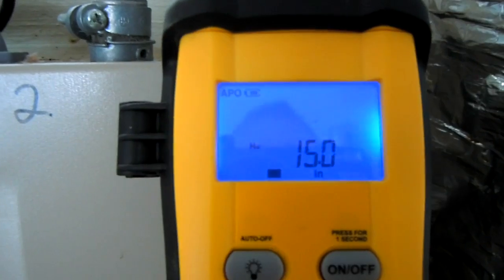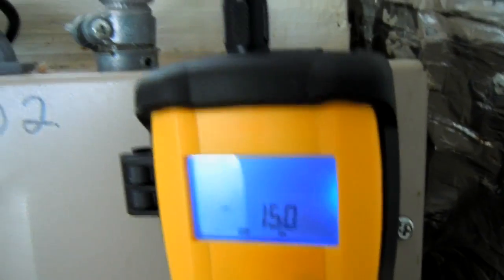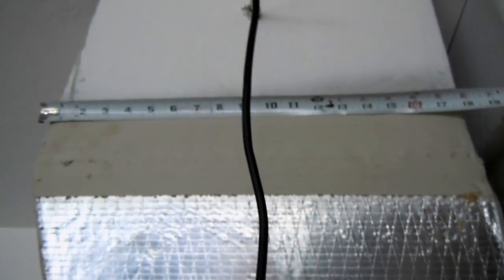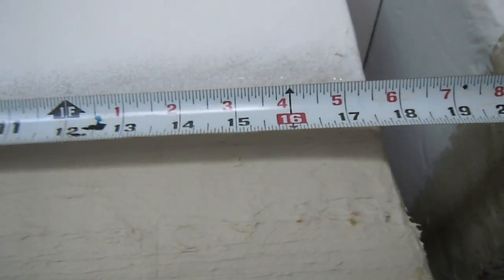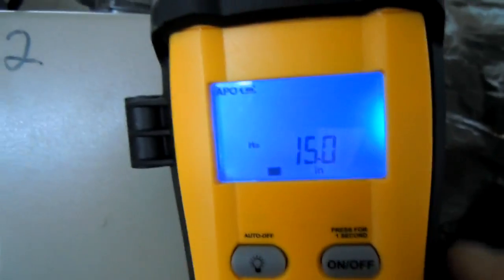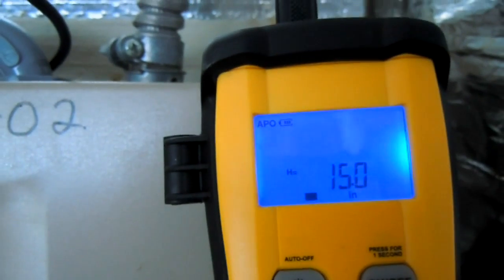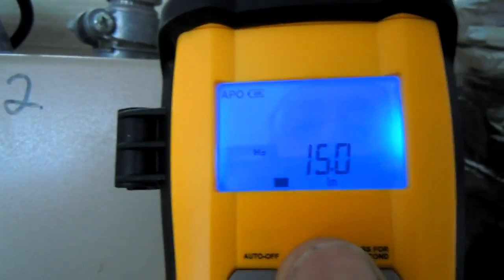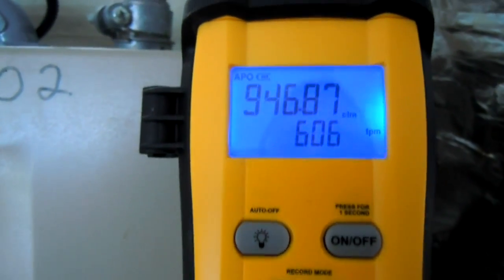In this case I've opted to go with the square duct sizing, and then you can hit enter again. What I have here is 15-inch duct, I have 15 inches of duct meaning a 15 by 15 square after you subtract the wall thickness of the duct board which is inch and a half all the way around. So instead of having 18 inches from here to here, we'll have 15 inches. 15 is going to be the height, and then I'll hit enter, and the width is 15 as well.